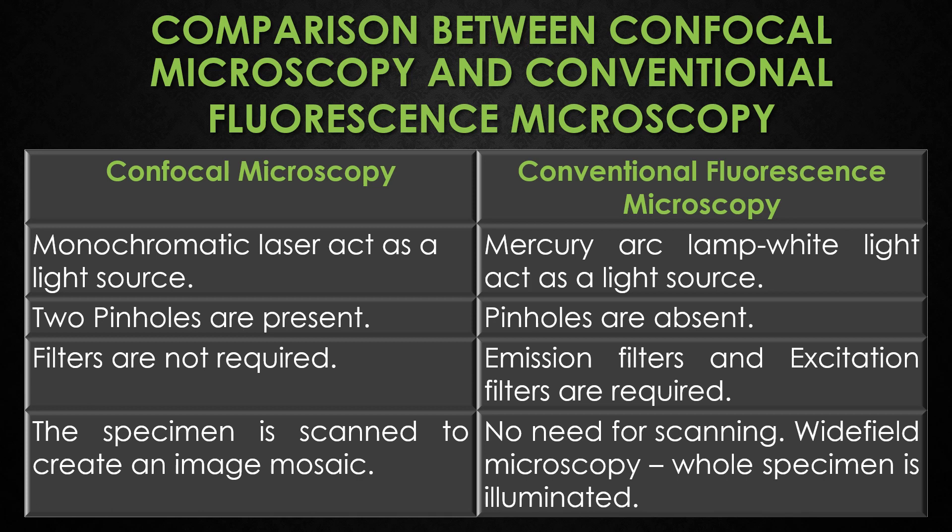Comparing confocal microscopy with conventional fluorescence microscopy: in confocal microscopy, a monochromatic laser acts as the light source, whereas in fluorescence microscopy a mercury arc lamp or white light is used. Pinholes are present in the confocal microscope but absent in the fluorescence microscope. Filters are not required for the confocal microscope, but the fluorescence microscope requires emission and excitation filters. In confocal microscopy the specimen is scanned to create a mosaic image, but in conventional fluorescence microscopy the whole specimen is illuminated.